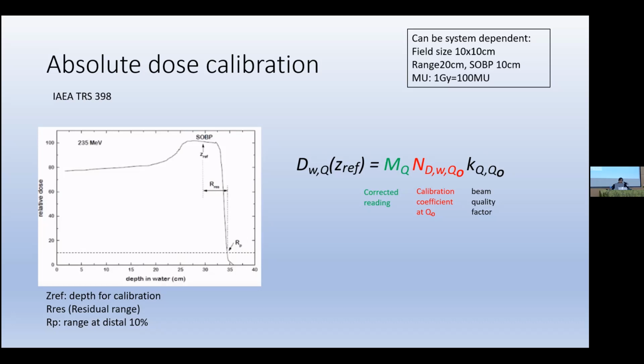And those of you that have done what I'll call the TG51 or TG21 type calibration, this MQ is all your corrected readings. So your ion chamber correction factors, your electrometer correction factors, the polarity, everything else all thrown in here. This is the calibration coefficient at your quality at Q naught. So that's kind of familiar with photon therapy. Your Q naught is like cobalt, so you try to transfer everything from cobalt. This KQ has what is going to be most of the physics in it. This is your beam quality factor.